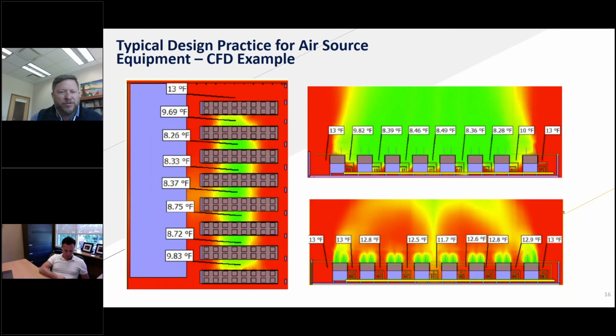Whatever the distance is in between, we have that square footage available for us to pull the air in. We also have, on the end of the units, however tall the units are by the width in between them, that small area that we can pull air in as well. But the problem that exists there, and the reason we see a lower temperature, it's just a reality, is because we can't pull enough fresh 13-degree air in.